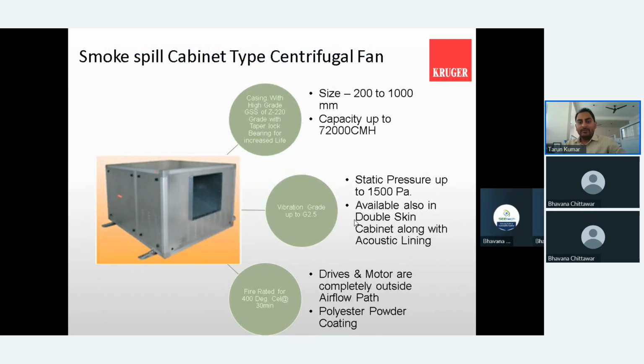Similar to that, we have one more, the smoke spill cabinet fan, which is used for kitchen ventilation as well as for any high temperature application. In this case, in certain cases, we have a separate cabinet inside the cabinet. One separate cabinet will be there for the motor, which will separate the motor from the airflow path. So here again, if you have a height restriction, or you do not have proper space to install, then we should preferably go with the DIDW fan in such an arrangement that the motor will be outside the airflow path.